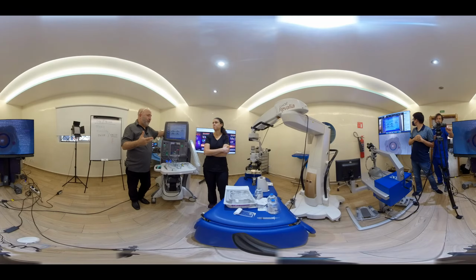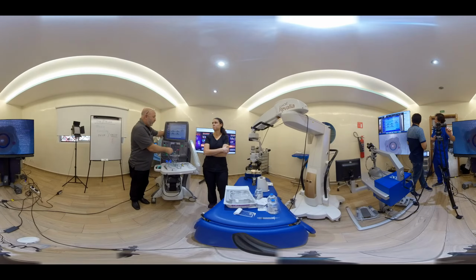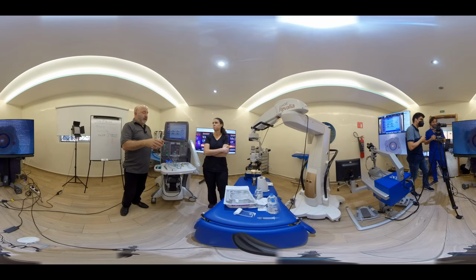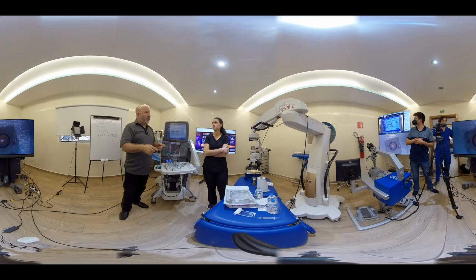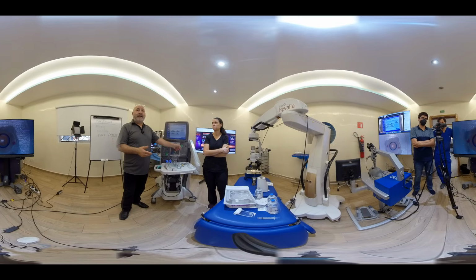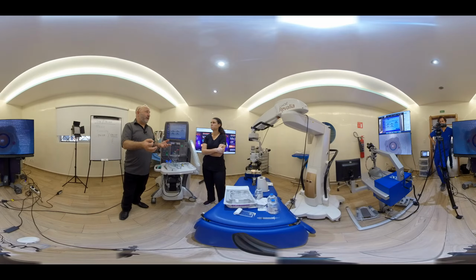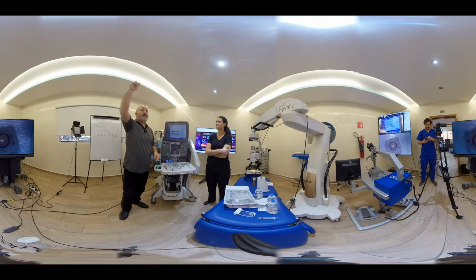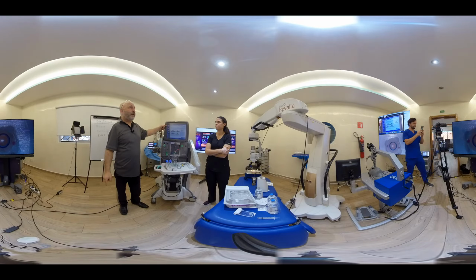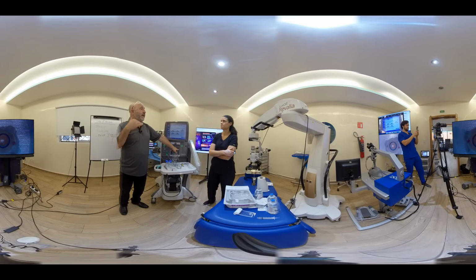So how does IOP work? IOP is measuring flow, infusion flow going to the eye. If I've got a leak, it sees flow coming in, and it says, there's a leak here. I have to increase the pressure in the infusion cassette, in the infusion chamber, because there's obviously a leak and I have to compensate for it. But what happens in an open sclerotomy is, all that happens is the fountain then grows. And then it says, oh, it's getting faster, the flow to the eye. And it says, oh, it's a big leak. So then it increases the pressure again. And it's a vicious cycle. And so you end up with this huge fountain, and you end up with 120 millimeters of pressure in the infusion chambers, trying to equalize the pressure in your eye.